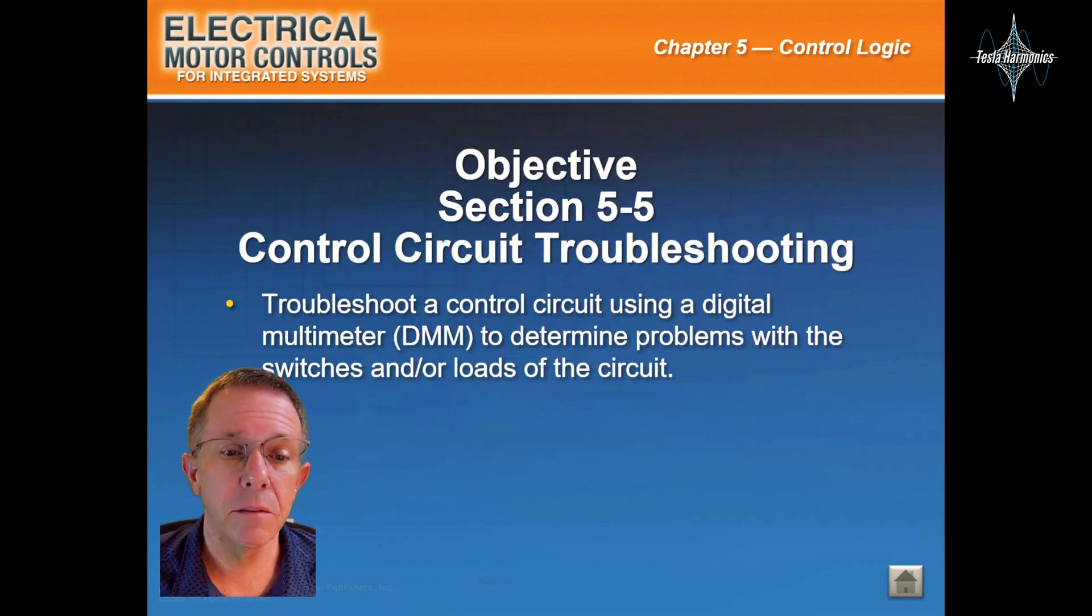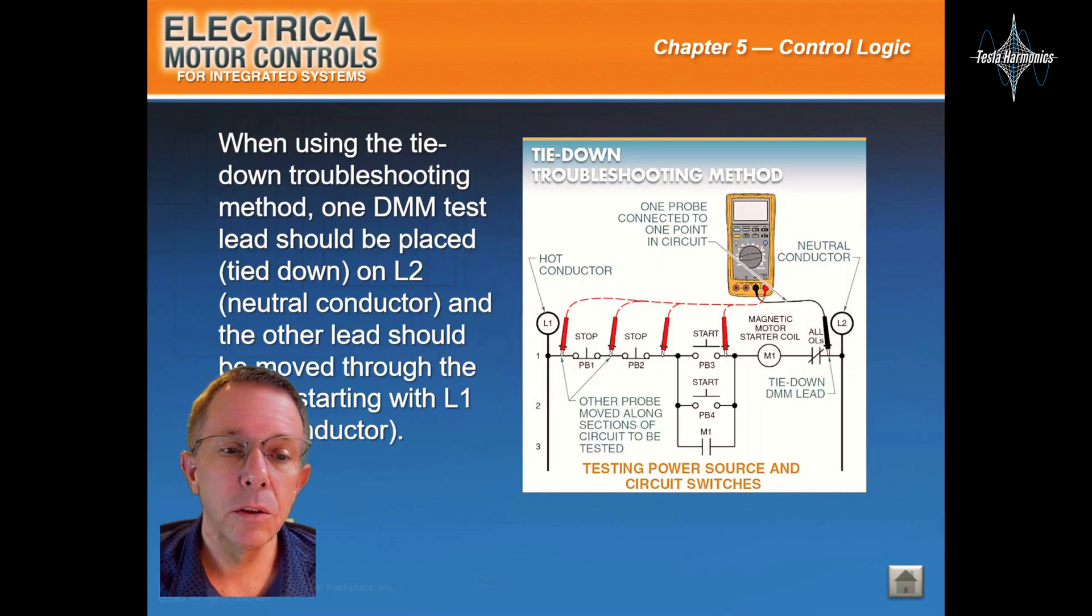This will be section 5-5, control circuit troubleshooting. When using the tie-down troubleshooting method, one digital multimeter test lead should be placed or tied down on line 2, or the neutral conductor, and the other lead should be moved through the circuit starting with line 1, the hot conductor.